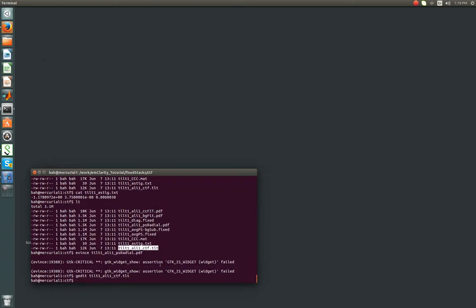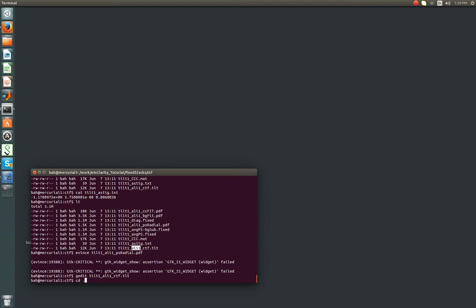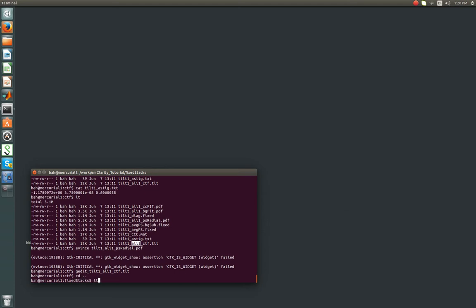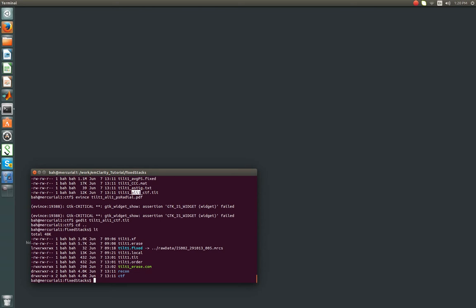So that is going to be prefixed and it can change throughout the experiment based on whether or not you've done any tomogram particle polishing. And for every time you do tomogram particle polishing, that number will increment by 1. And we'll talk about that in its own video. Basically, these files are here. You can explore these other ones, which are all centered around troubleshooting and assessing the quality of the fit. But we can see already just from the radial power spectrum that things look good. So from there, we've completed the CTF estimation.